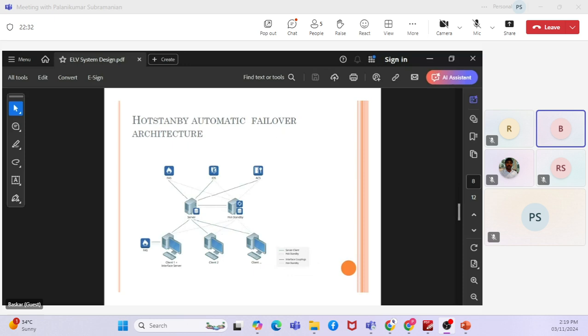Here is another type of architecture I have mentioned. What we have is a server and a hot standby server, and you can see that it's a failover architecture. Failover architecture means you have a server and multiple systems connecting to it. In case the server fails, within a short period, in milliseconds, the hot standby server should take over, and there should be no impact on overall performance. The changeover from the server to the hot standby server should not be noticed by any of the clients. That's how the system architecture is developed here.